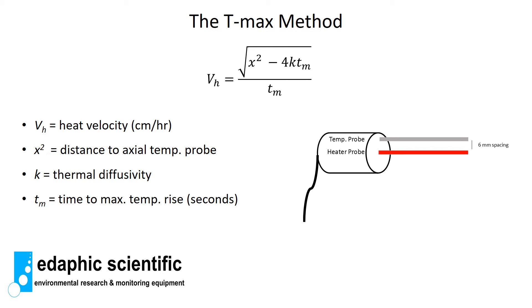The tmax equation is given here. Going back to high school physics, velocity equals distance divided by time, with some thermal properties included. In the equation, Vh is your velocity, x is the distance between the heater and the temperature probe (six millimeters or 0.6 centimeters in our case), tm is the time to maximum rise in temperature, and k is your thermal diffusivity. It's a fairly simple equation.